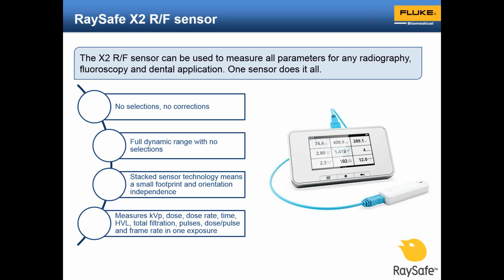From simple radiographic measurements to more challenging AMX portables to low-dose pulsed fluoroscopy to cone beam CT dental systems, the X2 RF sensor can measure on all of them without any special settings or selections. The stack sensor technology means a very small radiological footprint which won't drive up the dose when making measurements in automatic exposure or automatic brightness mode. The stack sensor also reduces the worry about heel effect and allows for orientation independence in the exposure area. Simply put, this makes it easy to position the sensor and get accurate readings every time.